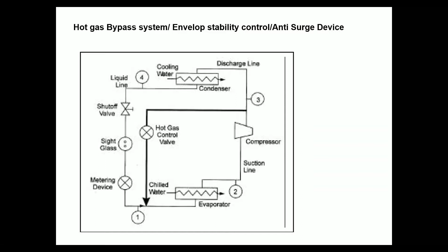But this is important, and with an intelligent, proper use of hot gas bypass, we can actually prevent a lot of catastrophic failure on a centrifugal chiller. We strongly recommend that this should be a part of the system. When it is kicking in, whether your centrifugal chiller is properly designed to handle the requisite lift is again dependent on the manufacturer or the person who is designing or selecting the centrifugal compressor. As long as that part is being taken care of, hot gas bypass can be present on the system as a safety device.